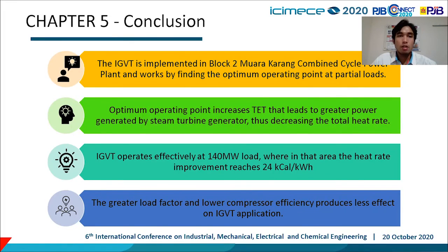Chapter 5, conclusion. The IGVT is implemented in block number 2 Muara Karang combined cycle power plant and works by finding the optimum operating point at partial loads. The optimum operating point increases turbine exhaust temperature that leads to greater power generated by steam turbine generator, thus decreasing the total heat rate. IGVT operates effectively at 140 megawatt load, where in that area the heat rate improvement reaches 24 kilocalorie per kilowatt hour.